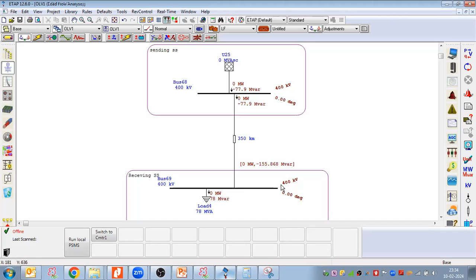Thanks, hello sir. Sir, what will be the case - we are using NGR, right, and if the shunt reactor is connected to a transmission line, so if there is a 3-pole auto-reclose - because in UK, sir, we use only delayed auto-reclose function - in that case also do we need NGR, or is NGR only required for single pole auto-reclose?